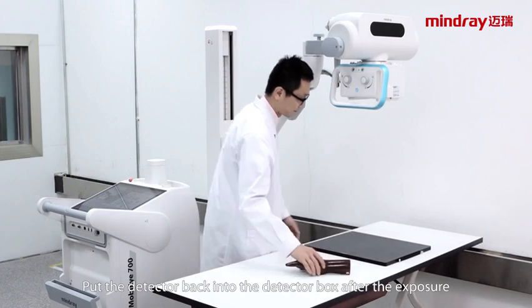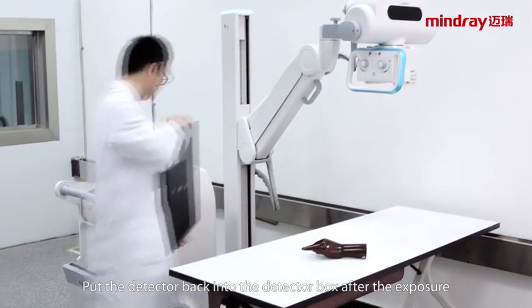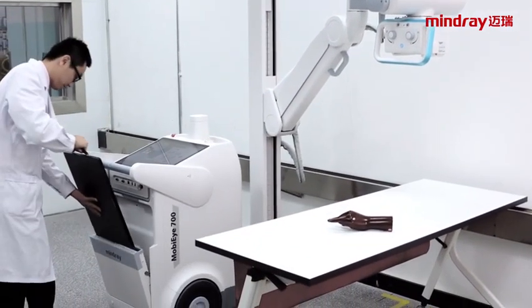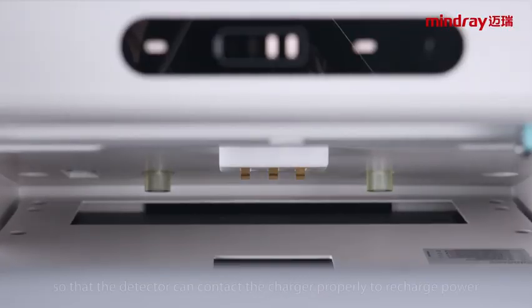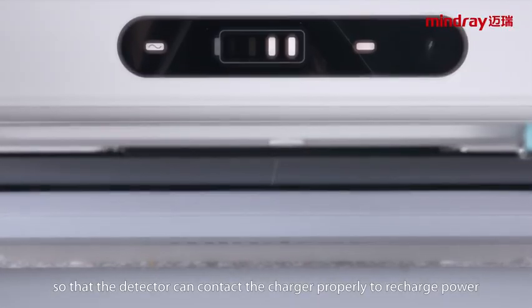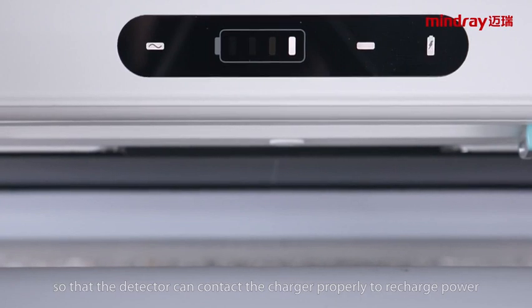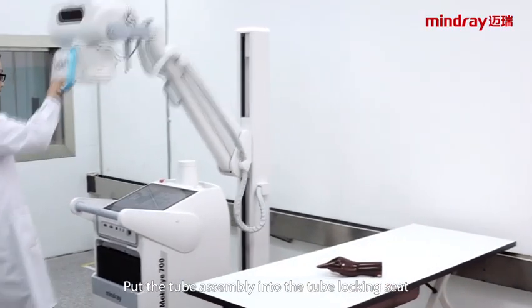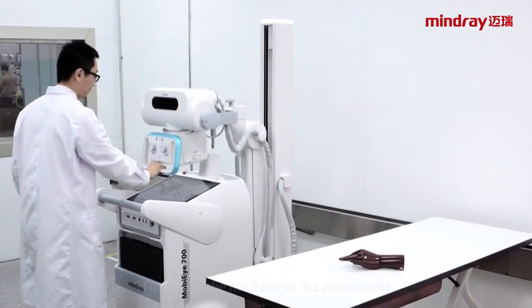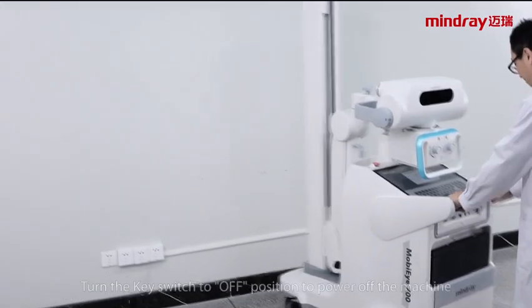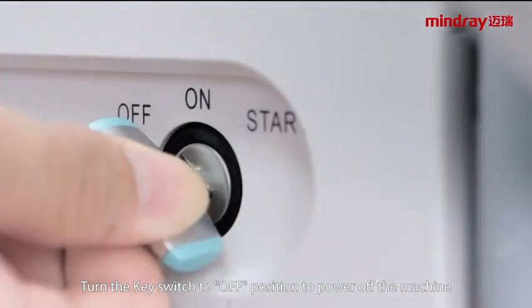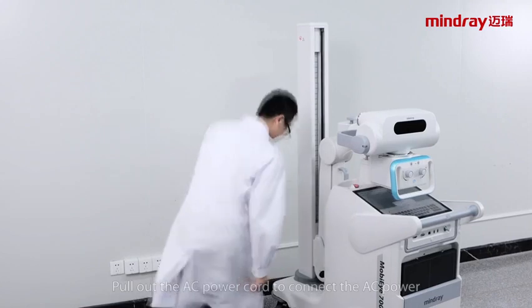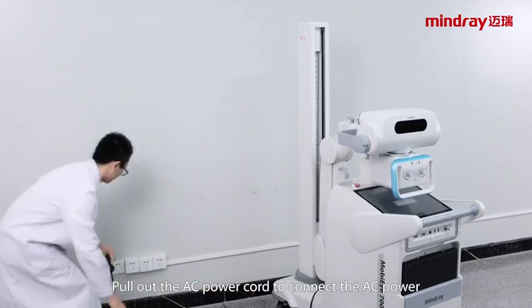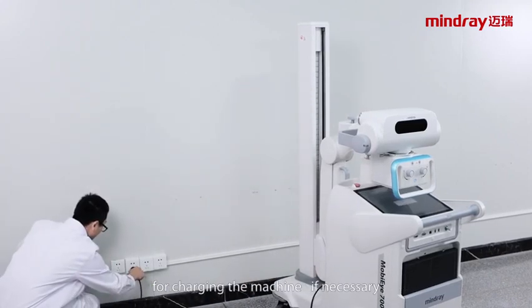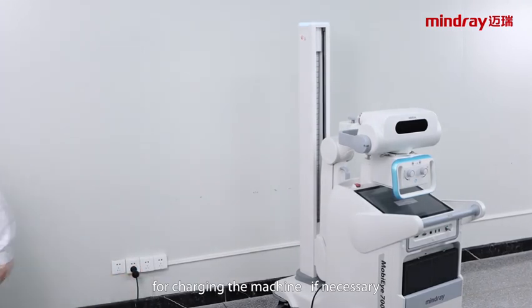Put the detector back into the detector box after the exposure. Close the detector box so that the detector can contact the charger properly to recharge power. Put the tube assembly into the tube locking seat. Then push the machine to the storage site. Turn the key switch to off position to power off the machine. Pull out the AC power cord to connect to the AC power for charging the machine if necessary.